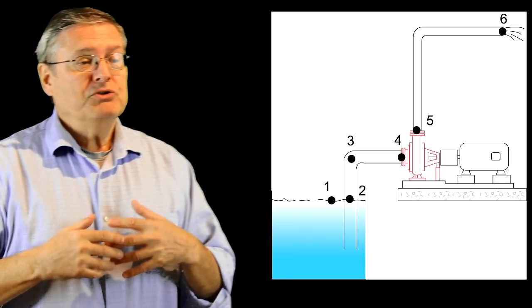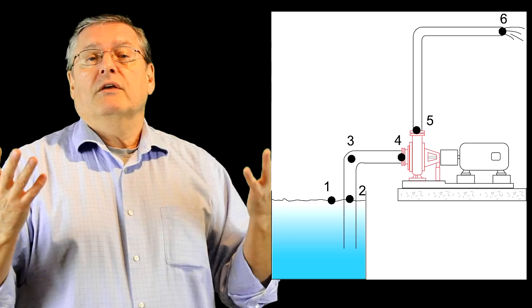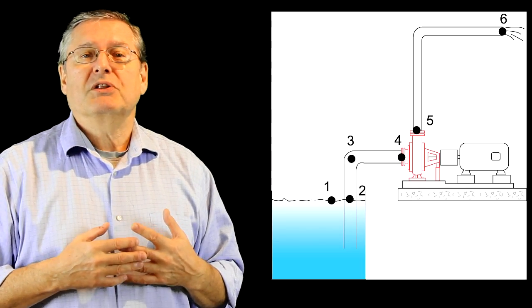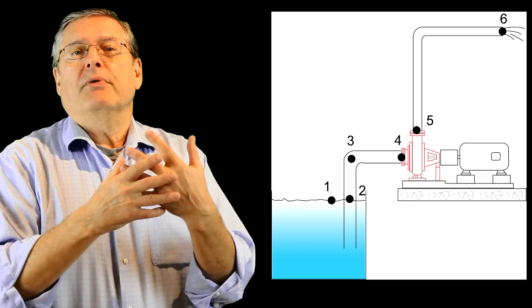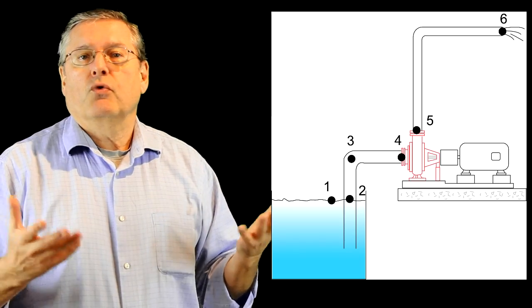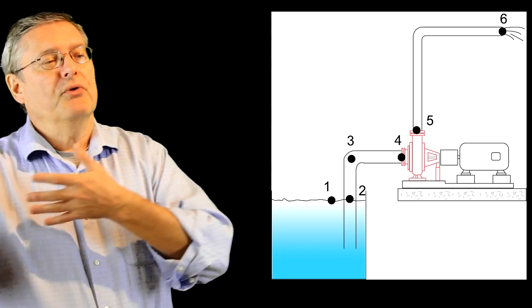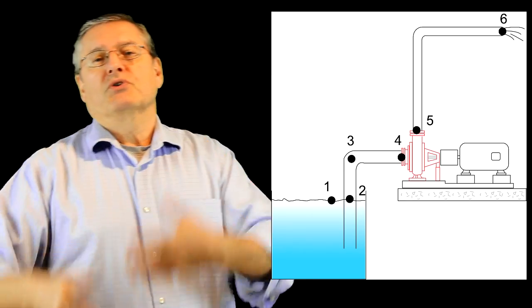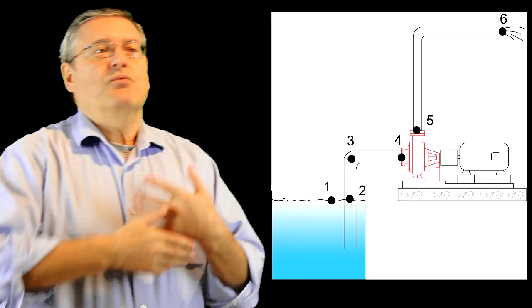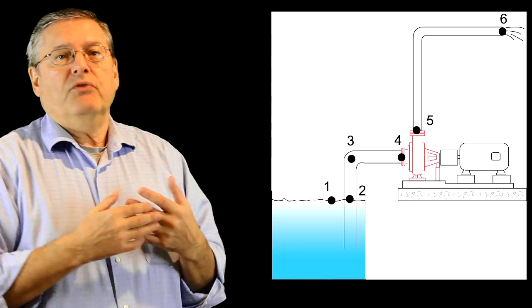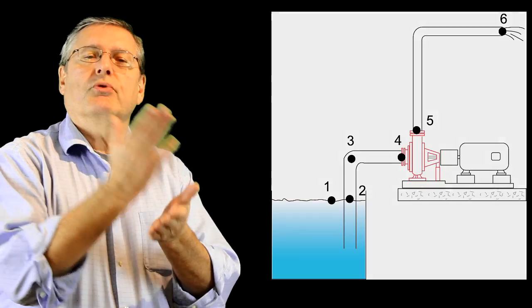There's a common misconception that pressure in a pump system is the same everywhere. Of course it's not — as we go up we lose pressure, as we go down we gain pressure, and as we come out to atmosphere at a pipe there is zero pressure. So even though there's a lot of flow, it looks like there's pressure, but there's actually no pressure at that point.